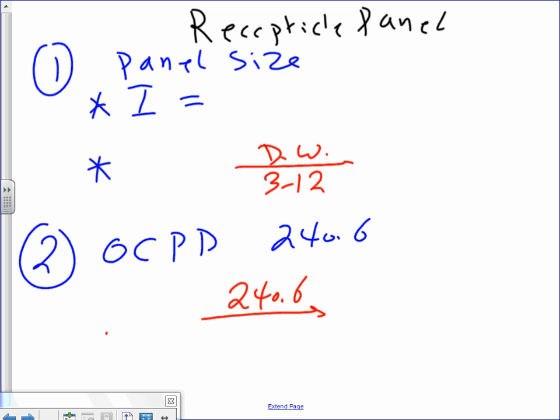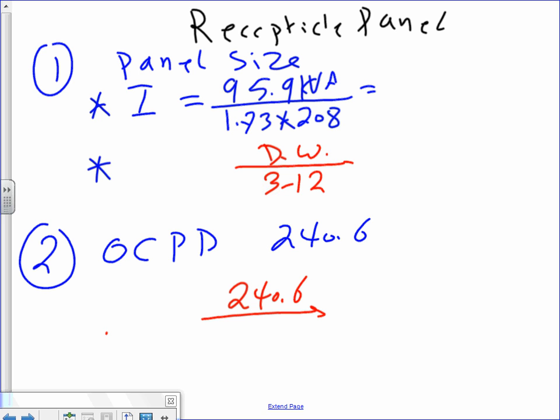Okay. Can somebody verify the panel size? Now we're doing the receptacle panel, gentlemen. What was the load for the receptacle panel? It was 95.9 kVA. Where did I get this number from? That big, nice table? So, KVA. I told you one of us is sleeping here. KVA, thank you, divided by 1.73 times 208. The whole system is 208. When you do your math, guys, you're going to end up with 267 amps.